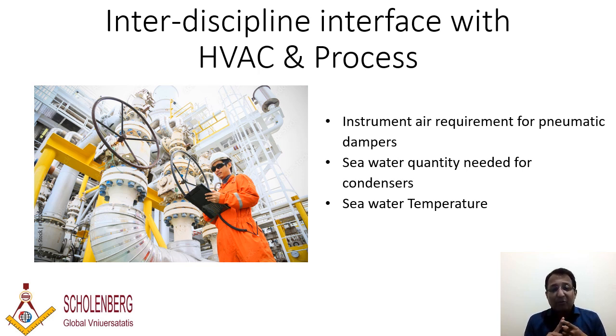So they can design the seawater pump for the entire platform. We need to tell them the seawater temperature our condenser needs. Once we get the temperature, we can select our condenser based on that. Second thing is that if you are using pneumatic dampers, of course you need air.